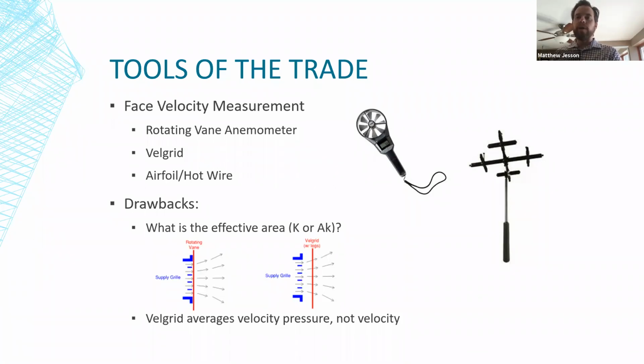this is where your effective area that we were talking about really comes into play. So you can see on these diagrams, the rotating vane is put up right against the surface of the grill, and you move it across the grill over time, to get an average of feet per minute across the face of a grill or register. So if you have that AK factor, you can pretty much rely on that. The VelGrid, however, if you put it right up against a surface of any kind, it kind of blocks those holes. You might be actually skewing it by doing that.